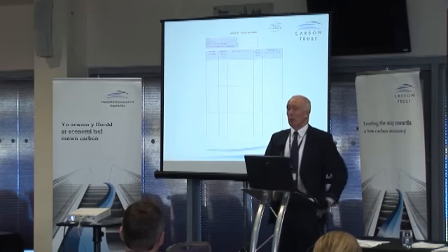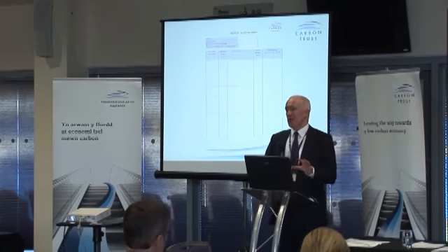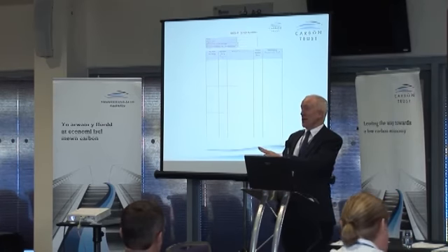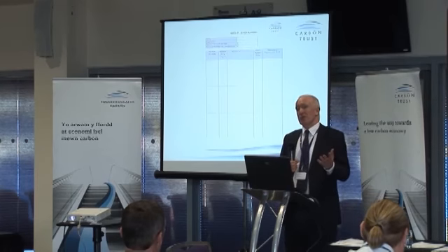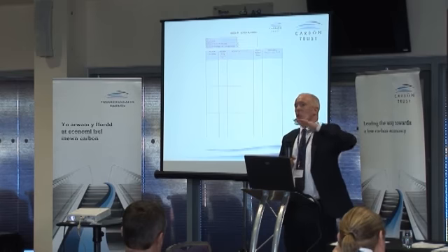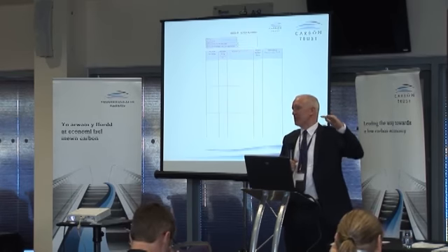So how could we utilise the waste heat coming out of our computer rooms? Really good question, and really interesting. You're saying it's next to a boiler house, which is really interesting. What you've got to realise is that when we're looking at waste heat recovery, we're looking at the grade of heat and the quantity of heat, and the grade of heat is actually the limiting step.